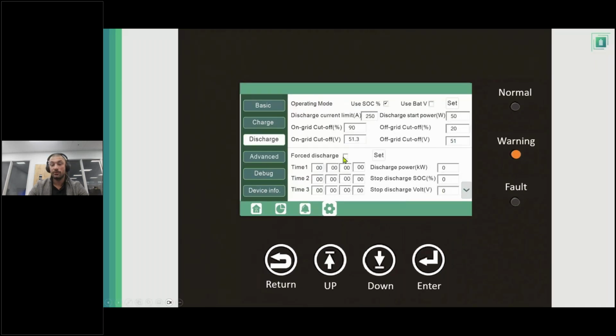Then there's force discharge, which is the one I'm going to use. Force discharge, and then discharge, let's say from 8 a.m. to 12 p.m. I am going to discharge from my battery, and to make sure that happens, I want to set this to as low as I want to go, 20%, 15%, to allow this force discharge to take into account. And then I'm also going to specify the discharge power, let's say 8 kW.